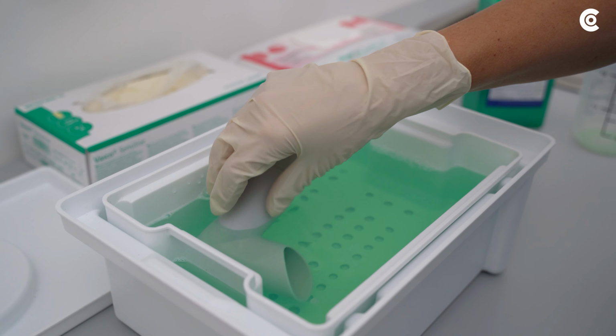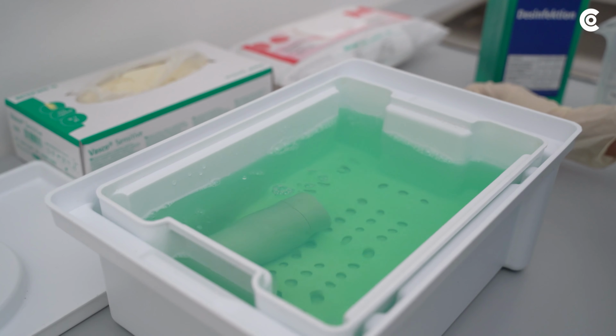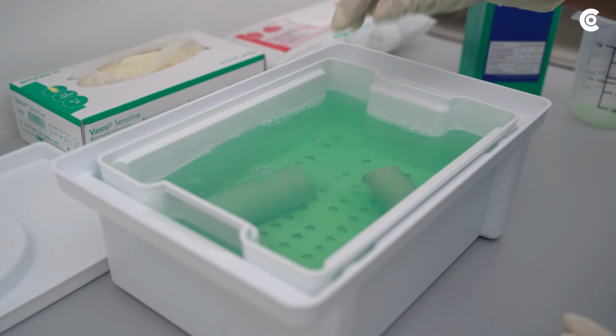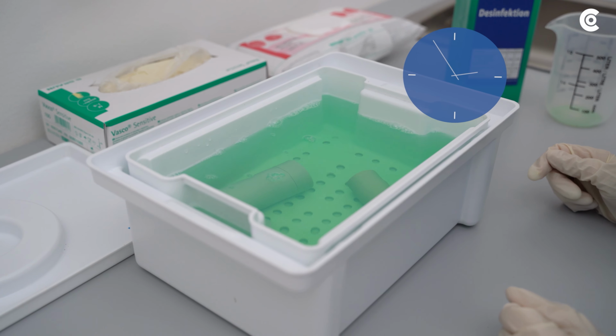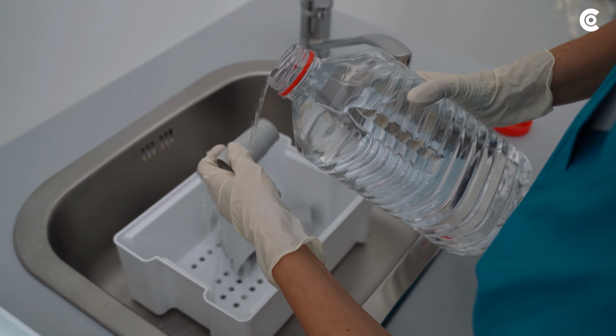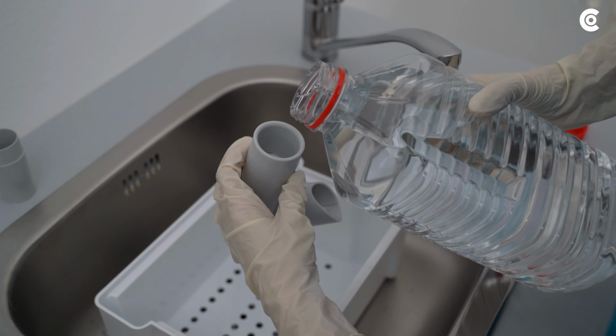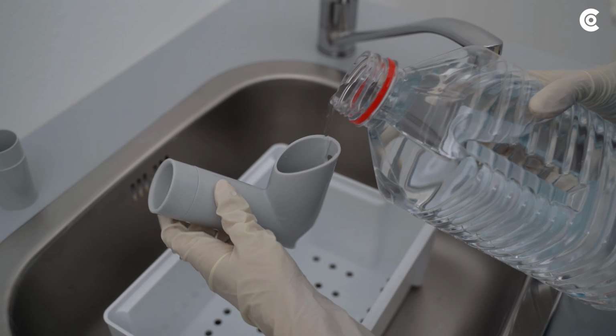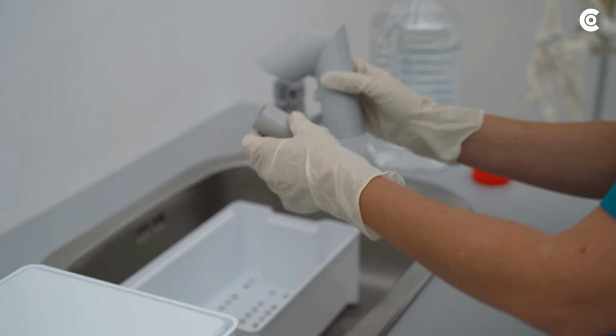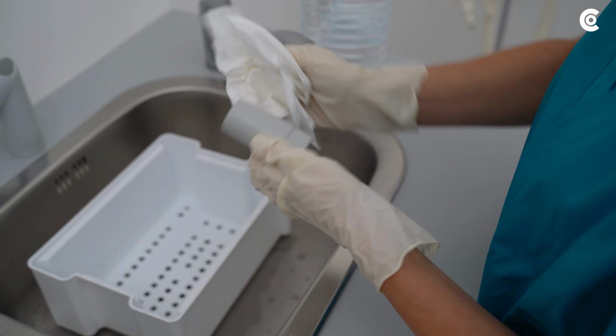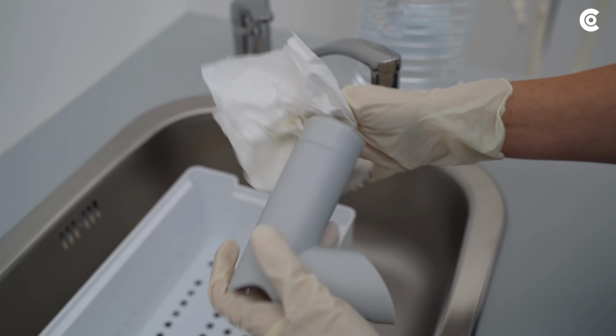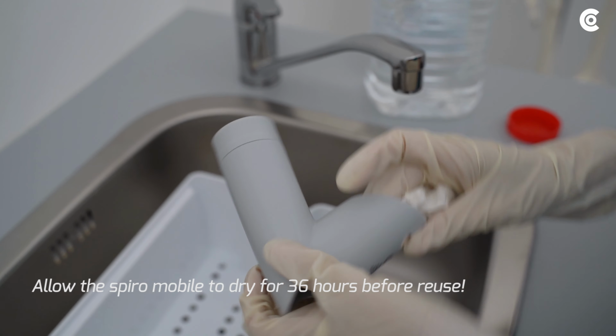Place the mouthpiece and the measuring head into the instrument tray and immerse it for the specified recommended application time. Now rinse the mouthpiece and measuring head with deionized distilled water and shake off residual water from the measuring head. Use a disposable tissue to wipe the surface. Make sure that no disinfectant residues remain in the device.